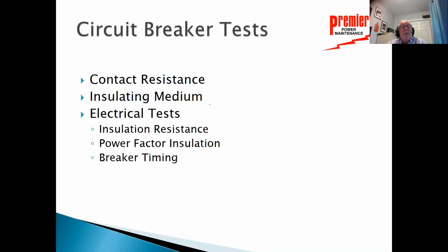Electrical test, again, always do insulation resistance. Power factor testing, to again look at the actual insulation of that breaker. And certainly breaker timing is a great indication that things are not moving as quickly or in the same manner that they did when they were new. If possible, when you do that breaker timing test, do it on the first operation of the breaker. You want to know how that breaker would have operated during a fault condition, and checking it on the first operation is your best chance of that.